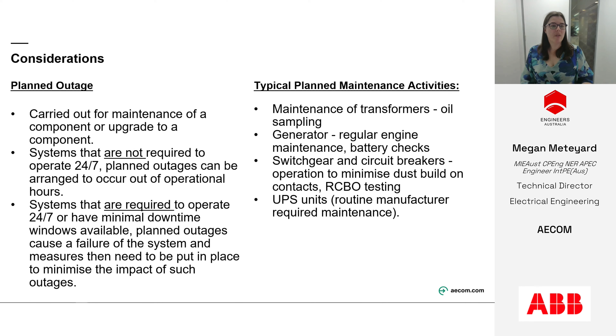But for systems that do operate 24/7, there's a whole series and sequence of planning and understanding of what alternative systems can be put into place to allow that maintenance to occur. There's some examples there on the screen of what that maintenance could be in a planned scenario. Maintenance of the transformers, taking oil samples, regular generator maintenance around battery checks and just routine engine maintenance. In your switchgear, circuit breakers, basic RCBO testing, cleaning, etc. And then UPS units all have routine manufacturer maintenance requirements. So all those are known things that can be planned into your system.